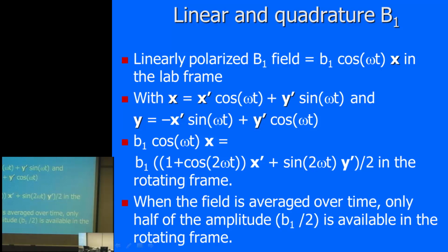So this is just the mathematical derivation. What's the meaning after this derivation? It means that your RF field in the rotating frame is effectively reduced by half. That's a bad thing, because in order to generate that field from a coil, you have to put in a current. Say I put this much current, I generate a field B1, but effectively it looks like B1 divided by 2, reduced by half. It means that if I still want a magnitude B1 field, I have to double my current.